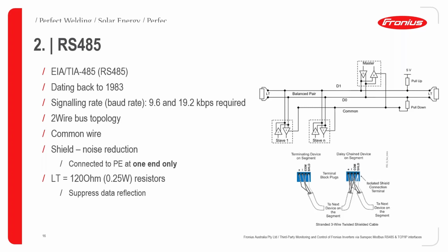This is coming from the protocol itself. The key point is that we typically use the 2-wire topology, a 2-wire bus obviously. Then you have 4 communication lines there: a plus, minus, a common, and a shield. Technically, that's 3, but don't forget the shield as well. The shield is only connected at one point, and the comms line is usually connected at the master, as well as every point, obviously.